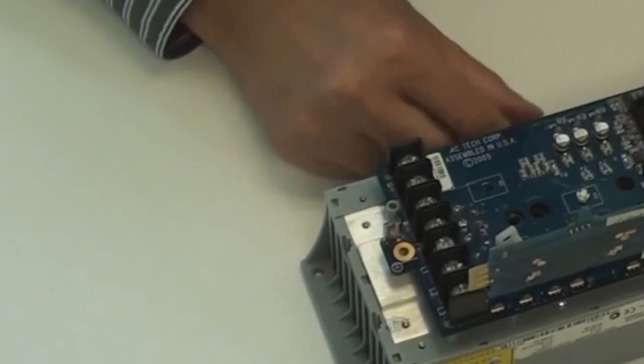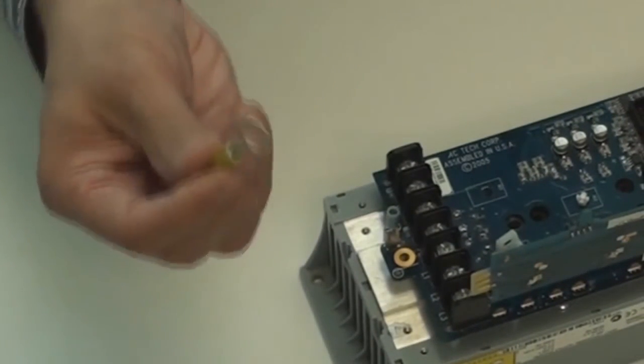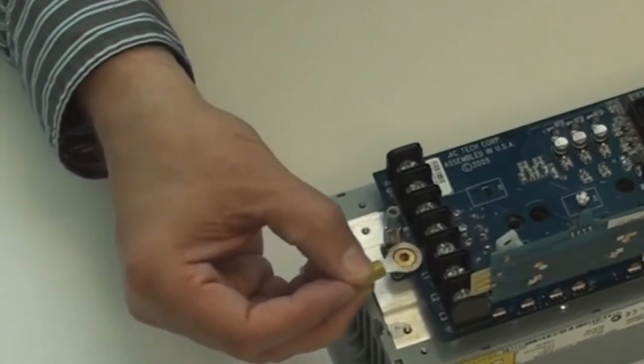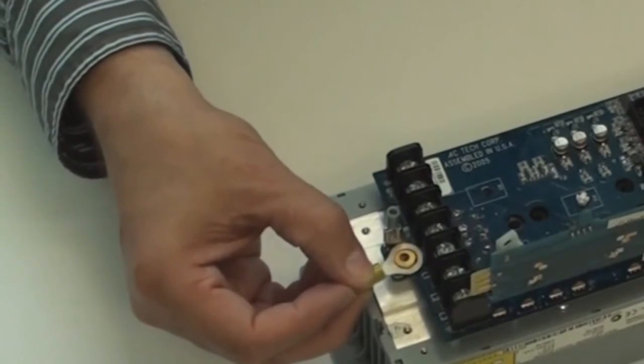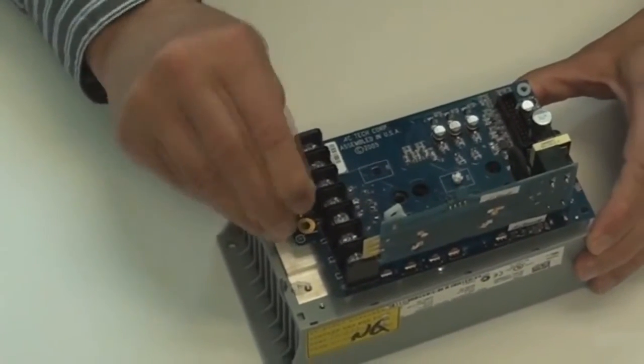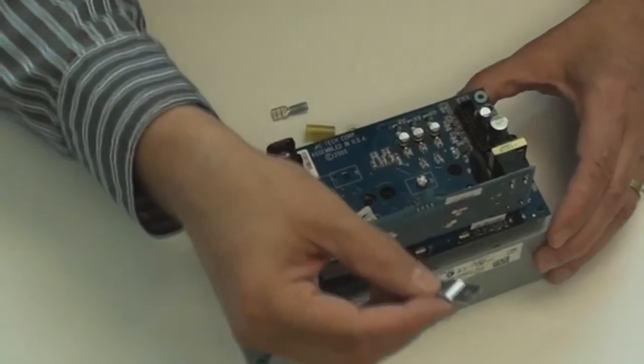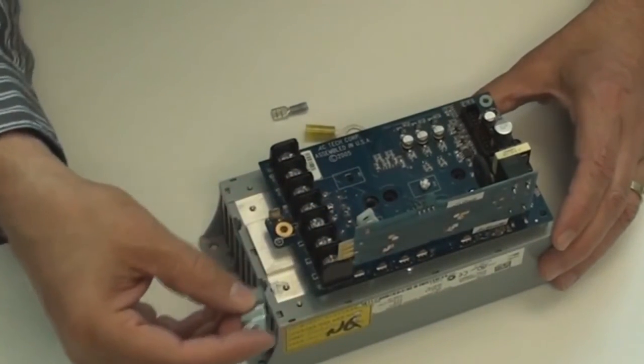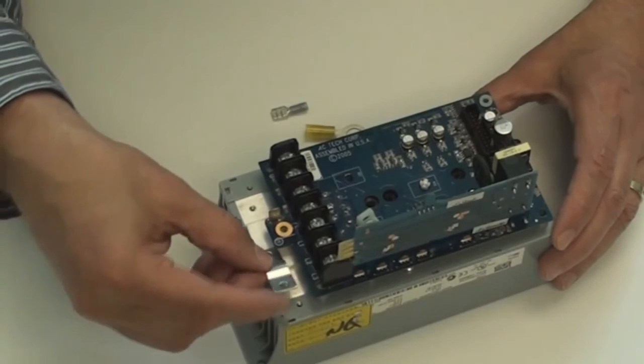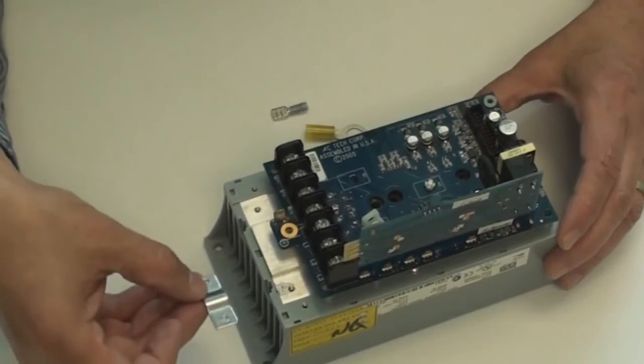You can also use an eyelet on the end of your cable if you have that type of ground connection back to your motor, and you would just connect it there, and then the screw would clamp down on that with a washer. And then the last thing is to use this small backplane, which is also like a saddle clamp, that will allow the drive cable to connect directly to either the body of the drive or further down into the panel of the machine.